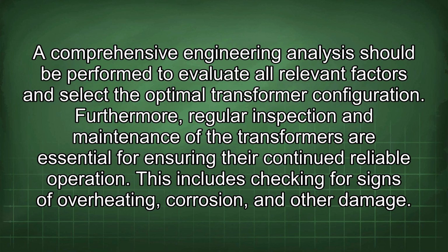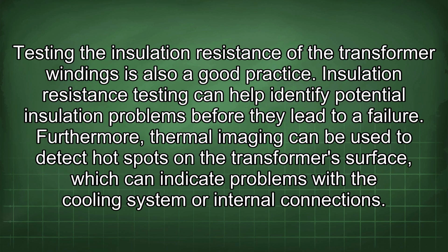This includes checking for signs of overheating, corrosion, and other damage. Testing the insulation resistance of the transformer windings is also a good practice. Insulation resistance testing can help identify potential insulation problems before they lead to a failure. Furthermore, thermal imaging can be used to detect hot spots on the transformer surface, which can indicate problems with the cooling system or internal connections.